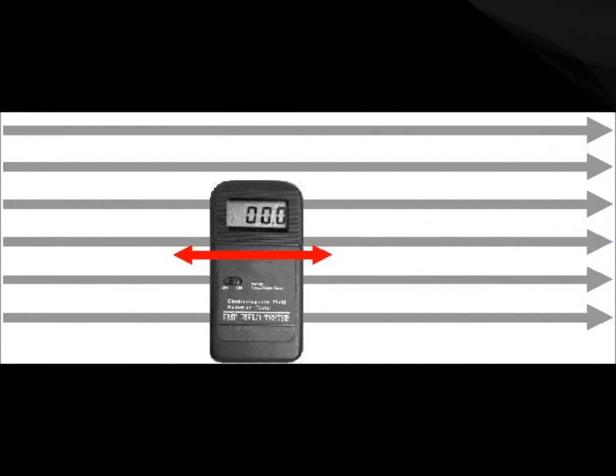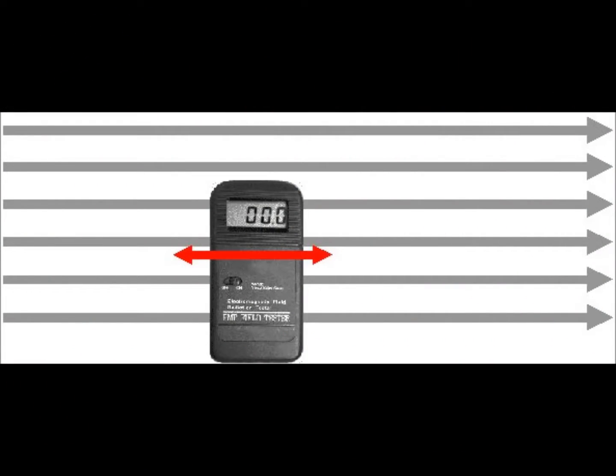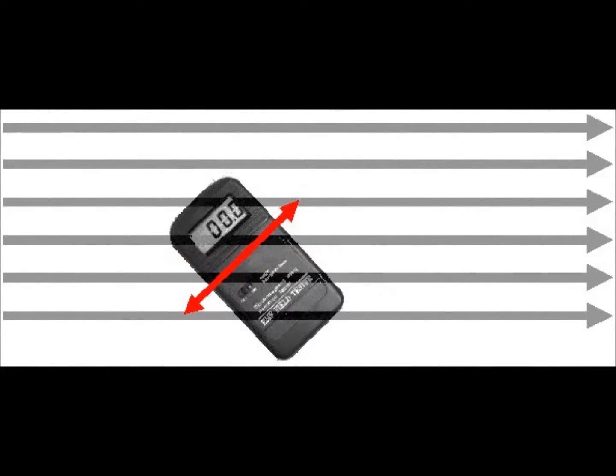The sensor in a one axis gauss meter only looks in one axis. Because magnetic fields are oriented in space, the sensor within the meter can only detect the field properly if it is aligned with the field.